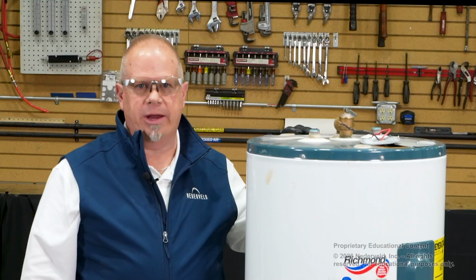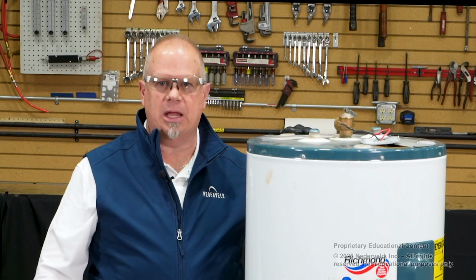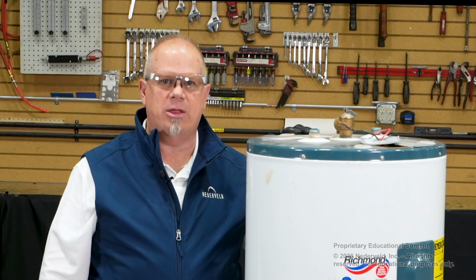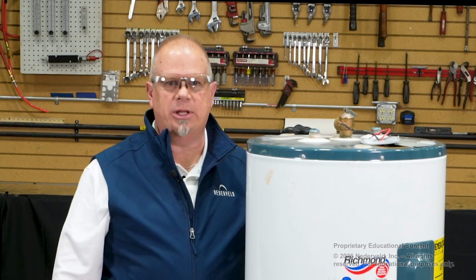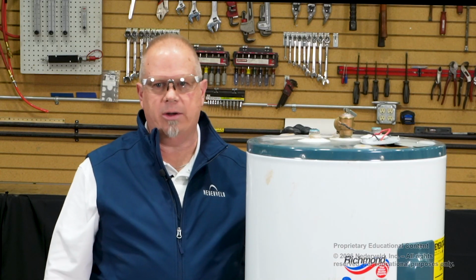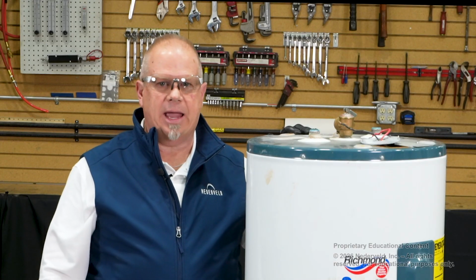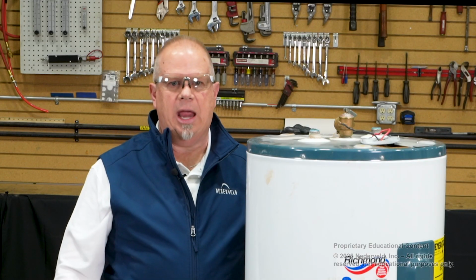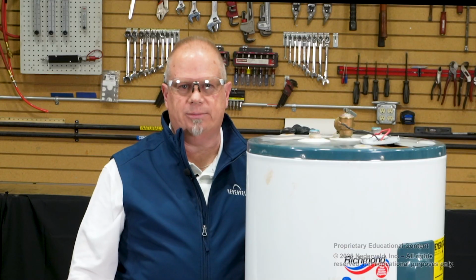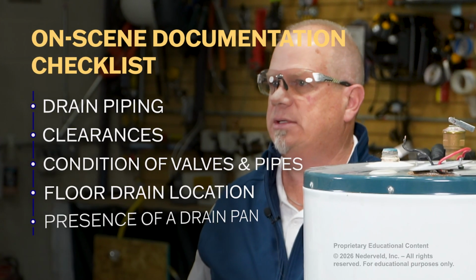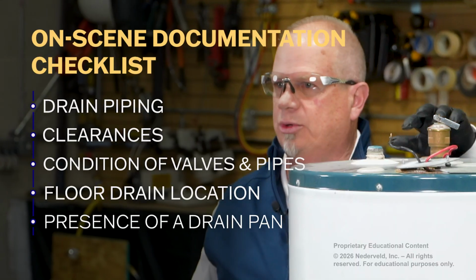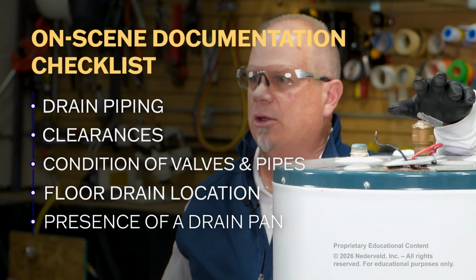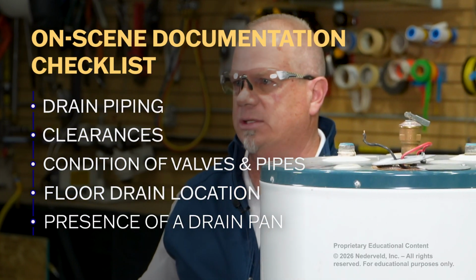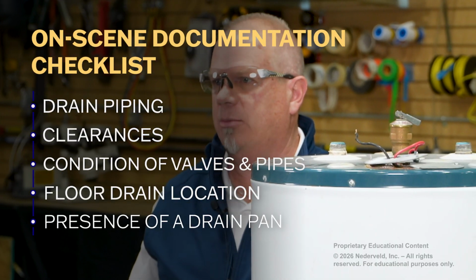When installing a water heater, the manufacturer's installation instructions must be followed, as they are stated in commonly used codes. A tank water heater is to be installed inside a pan with a suitable drain and water damage resistant materials. The drain piping, clearances, and condition of the temperature and pressure relief valve and piping, location of a floor drain, and presence of a drain pan should all be documented on scene prior to the removal of any water heater.